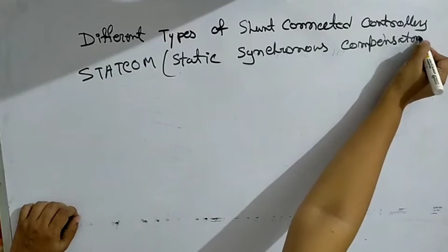It is a static synchronous generator operated as a shunt compensator whose capacitive or inductive output currents are controlled to control the bus voltage with which it is connected. Okay. Now STATCOM operation is based on the principle of voltage source or current source converter. So I first draw the schematic diagram of VSC type STATCOM and CSC type STATCOM.